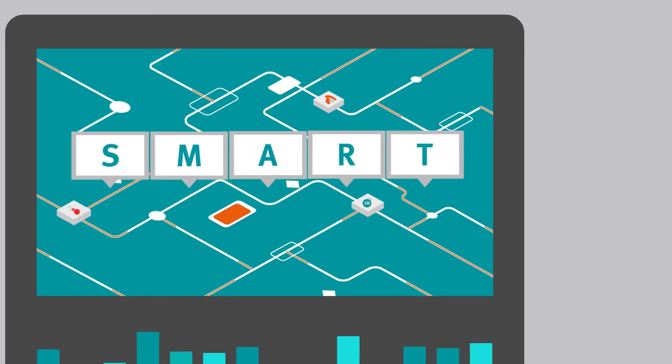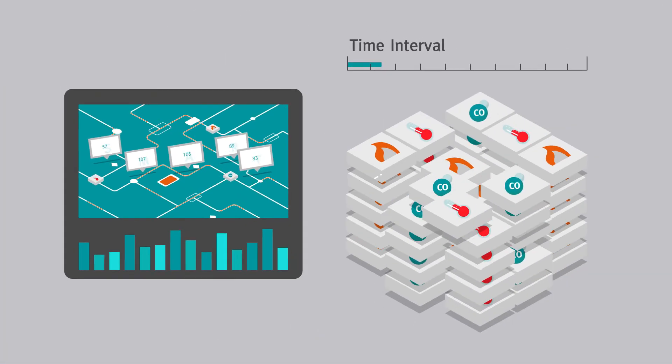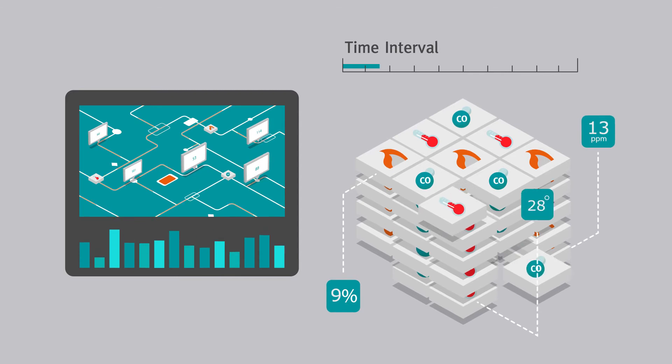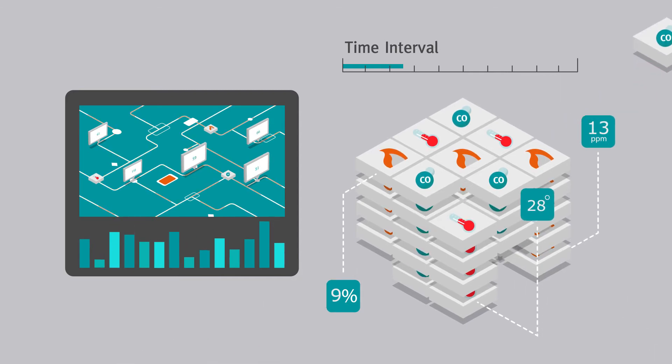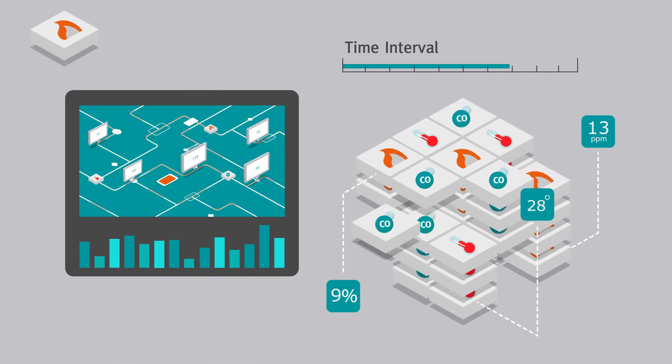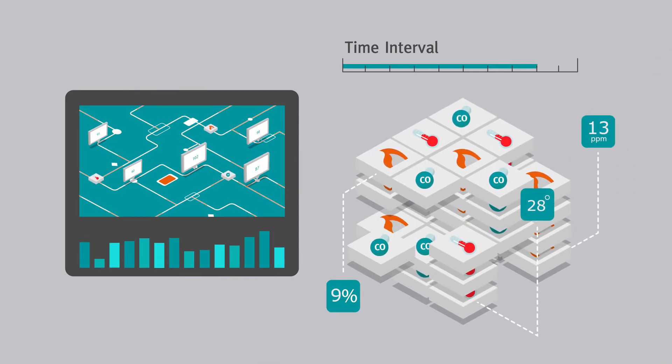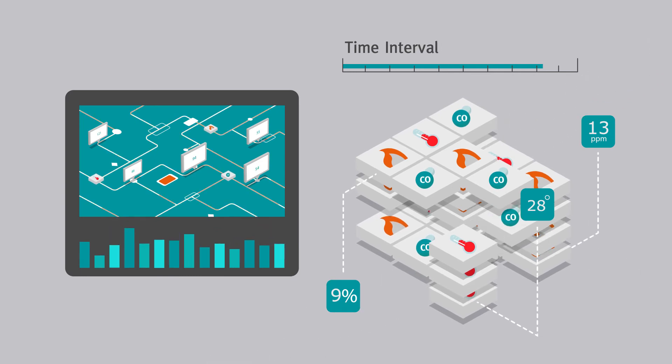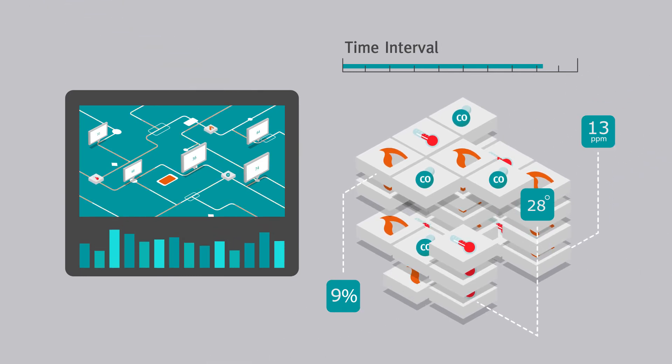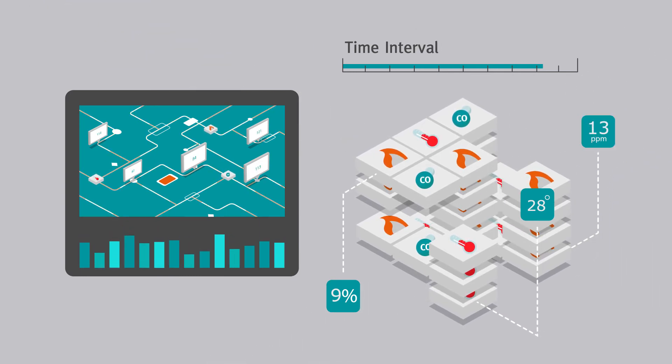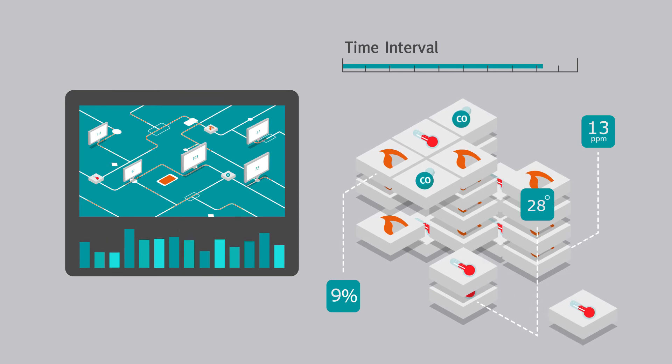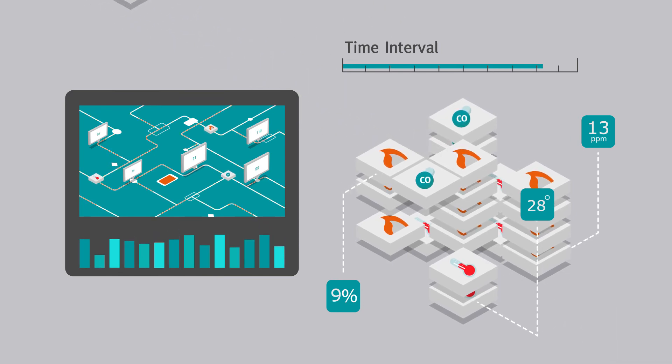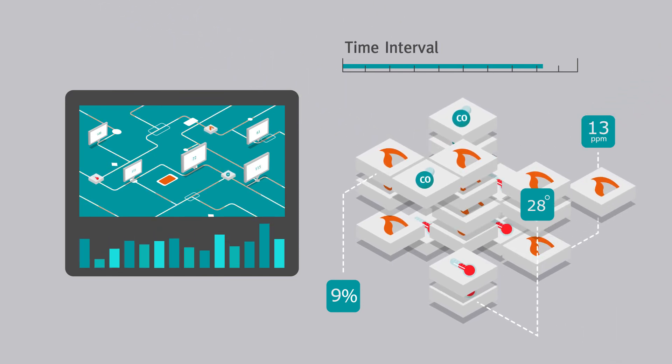If no transient activity is detected within a set time period, the number of samples used to calculate the moving average is reduced, in effect adjusting the sensitivity of the sensor to its environment. If the environment remains clear for another set period, the number of samples used is reduced again.